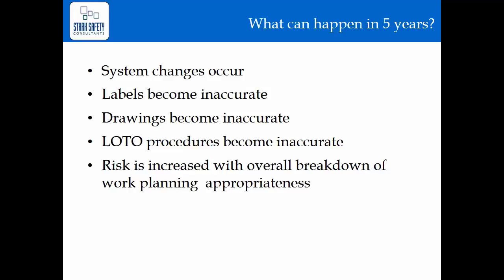Simply looking at what can happen over five years — this is going to depend on what type of system you have. If we take a real common, ever-changing environment such as a manufacturing plant, this makes it all well and true. System changes occur: machines get moved, equipment gets added, equipment gets removed, expansion, remodeling, downsizing — all those different things that can change the system. Your labels may become inaccurate. How often do you have equipment that's been added since the last study, and you potentially don't even have anything other than a generic warning label on that piece of equipment? No information about hazard or risk. So the labels become inaccurate or there are missing labels.